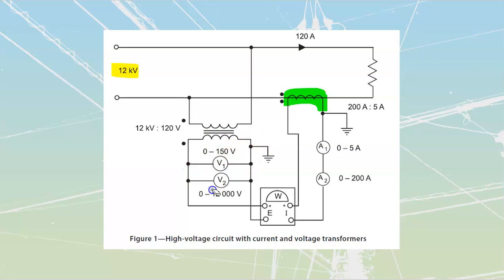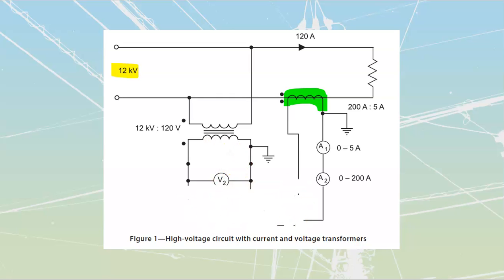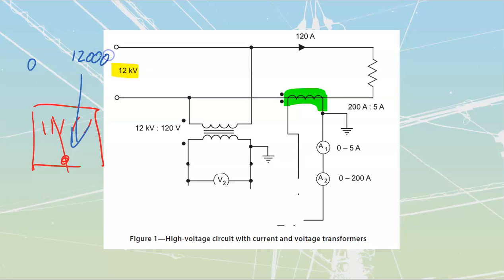If we take a look at the next voltmeter that is inside of here, and we'll just erase everything downstream here and ignore this one, the next voltmeter that's inside of there is going to be rated for 12,000 volts. It is not actually rated for 12,000 volts. What it is, is just that the paper in the back side of that meter, how we have these little hash marks on the paper over there, the meter movement itself is going to be 120 volts. But all that they've done is they have replaced the paper in the back, and instead of having a scale that goes from 0 to 120, they now have a scale that goes from 0 to 12,000. Still the exact same 120 volt meter though.